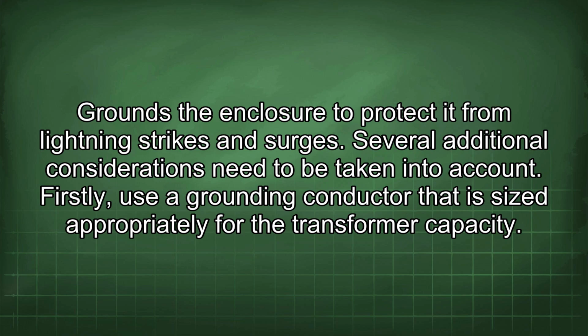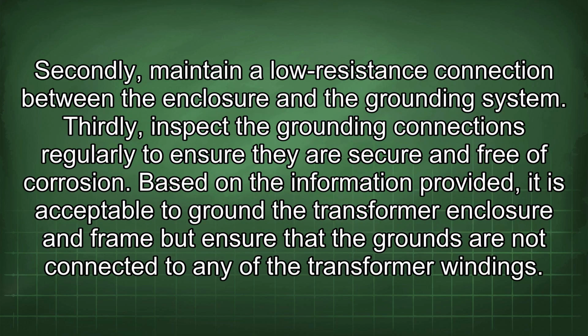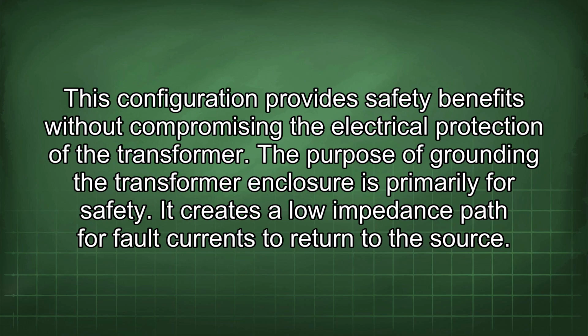Several additional considerations need to be taken into account. Firstly, use a grounding conductor that is sized appropriately for the transformer capacity. Secondly, maintain a low resistance connection between the enclosure and the grounding system. Thirdly, inspect the grounding connections regularly to ensure they are secure and free of corrosion. Based on the information provided, it is acceptable to ground the transformer enclosure and frame, but ensure that the grounds are not connected to any of the transformer windings. This configuration provides safety benefits without compromising the electrical protection of the transformer.